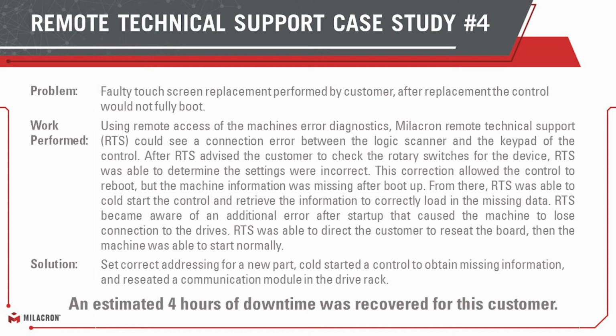Unfortunately, when the control tried to reboot several times, it caused some of the memory to become corrupted. Usually we can retrieve missing values with a soft start or a cold start on the control, and we're able to do that remotely as well. We assisted this customer with a remote cold start, something the customer could do themselves. They have to get a keyboard and know some simple commands, but it's also something we can do relatively easily in just a couple of clicks remotely. We were able to help them cold start, and the control booted up successfully.